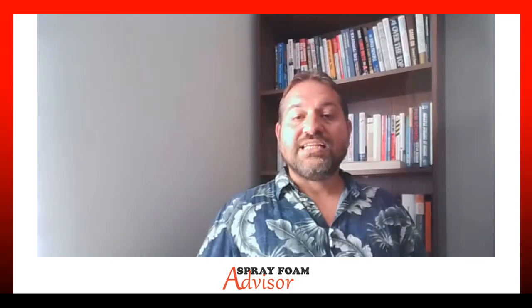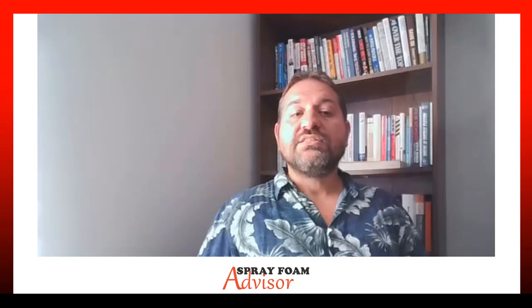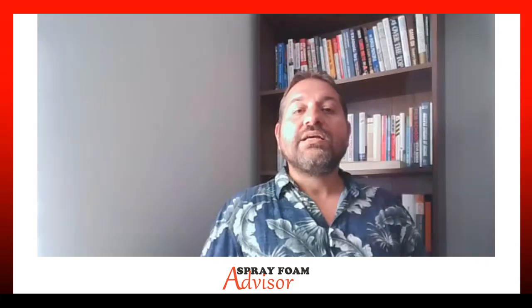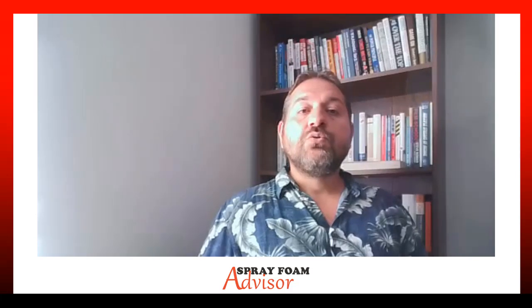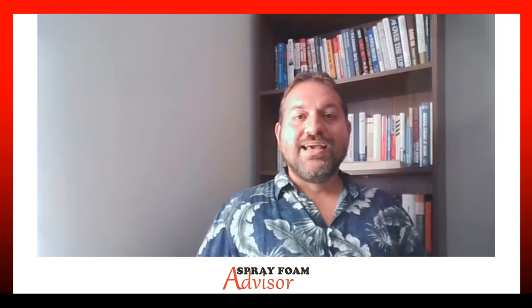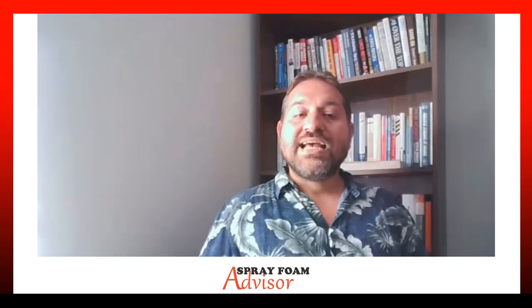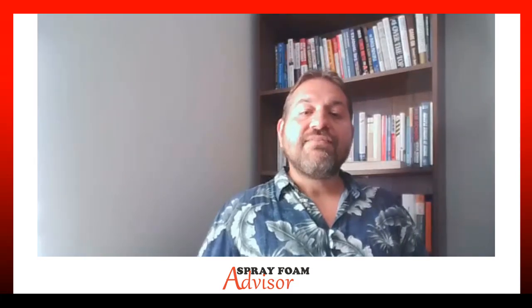So, if you are changing the building enclosure, such as adding spray foam insulation in a residential retrofit, it is critically important that you pay attention to combustion appliance zone safety, or CAZ safety. Everyone involved in the project, you, the owner, the general contractor, and everyone else involved in the project should have a discussion about combustion appliance zone awareness to discuss how tightening the envelope might affect any combustion appliances on the premises. Let's look at an example.